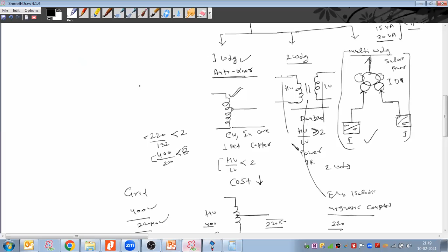Okay, ICT bay means interconnecting transformer bay, means transformer bay. ICT bay means transformer bay in simple words. Why is this bay called the ICT bay? Because they are using the single winding auto transformer, and HV and LV are electrically connected. Electrically connected means interconnected transformer. It means they will use an interconnecting transformer here.